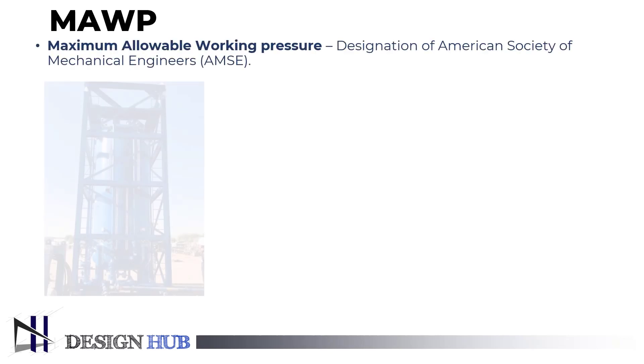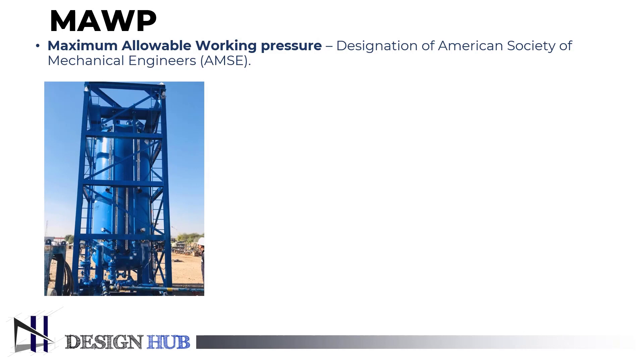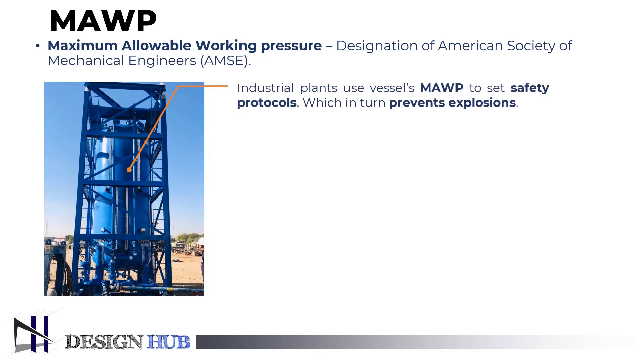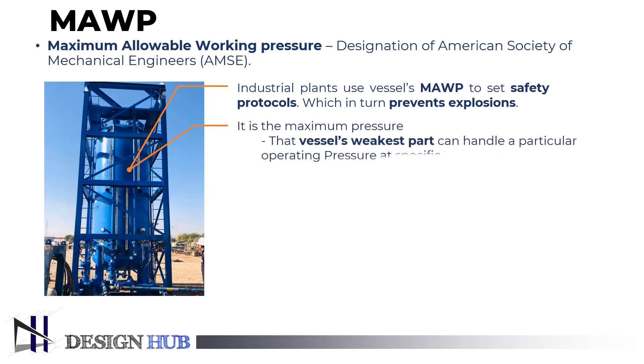Maximum allowable working pressure is a designation of the American Society of Mechanical Engineers and specifies the rating of the pressure release component of a vessel. Industrial plants use the vessel's maximum allowable working pressure to set safety protocols by ensuring that the system does not exceed its safe operating pressures, which in turn prevents explosions. It measures the maximum pressure the vessel's weakest part can handle at a particular operating temperature.